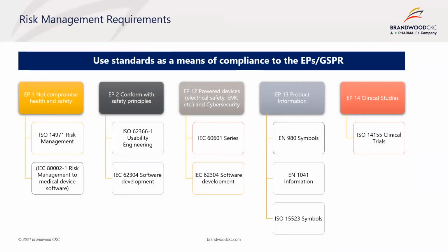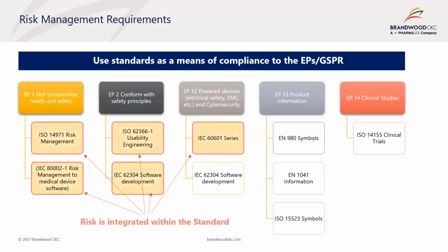The question may be asked, how do you show compliance to the Australian essential principles or European general safety and performance requirements? The primary method is by applying accepted international standards. Shown are examples of several Australian essential principles here, EP 1, 2, 12, 13, and 14. For each EP, I have listed the standards that can show compliance to the requirements. Of course, these will vary for each product, but here are examples shown for a typical active device incorporating software. Risk management explicitly covers several requirements, for example, EP 1 and 2, and indirectly for requirements such as EP 12. That is, risk is integrated with many of the standards that can be applied to show compliance to the requirements.